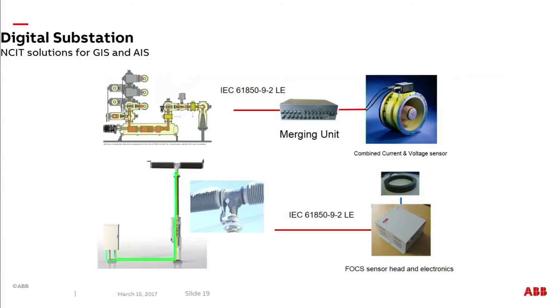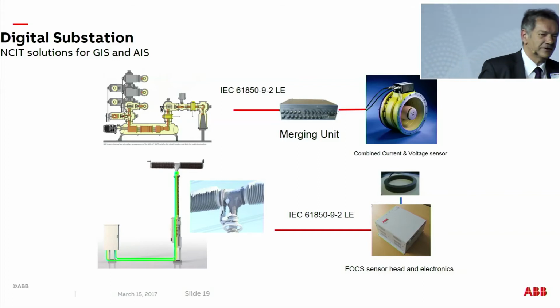What does it do to the primary equipment now? Once you have these sensors, you can integrate them into the primary equipment much, much easier. This is an example of a gas-insulated switchgear, where you see here a current and voltage sensor, and here a current and voltage sensor. And in air-insulated, you see an optical sensor, and this optical sensor works based on a polarized light beam, and the polarization angle of light is changed as a function of the magnetic field. This is a quantum physics effect, which many people understand, not me, but it works.